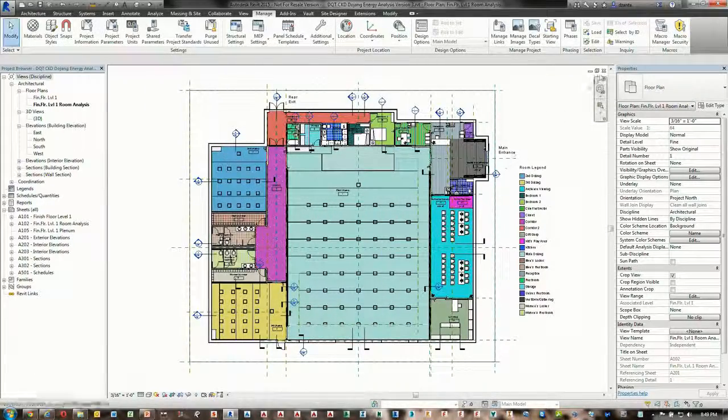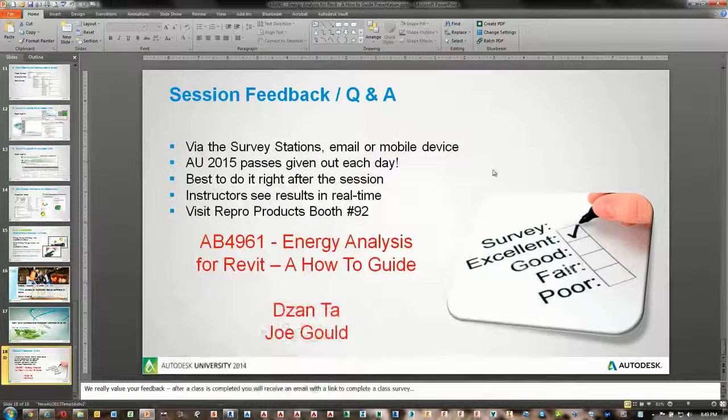I can't really release their name, but they were redoing a lot of federal buildings and then comparing. They were using Vasari, which is basically the same thing. They were within 11% of historical utility bills when they gathered the data from here and then went back and compared it. So they were within plus or minus 11%. Can you fine-tune that and get it down even more? Absolutely. But for them, they just needed to get some quick numbers and then contrast. But yeah, 11% was not bad.